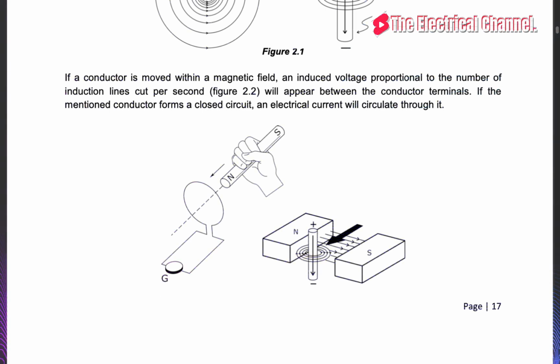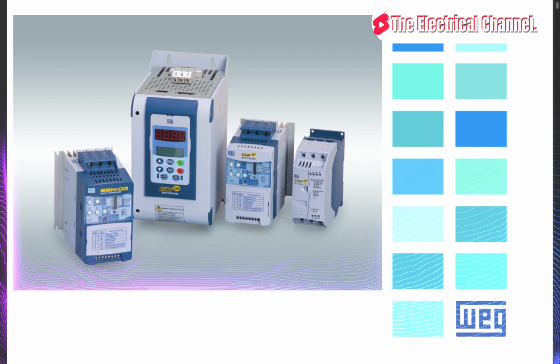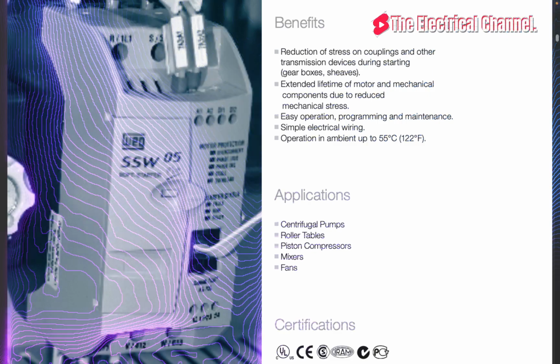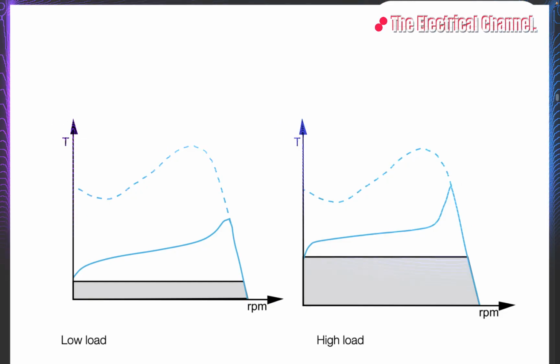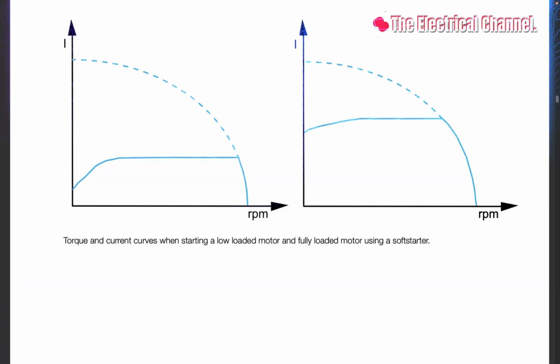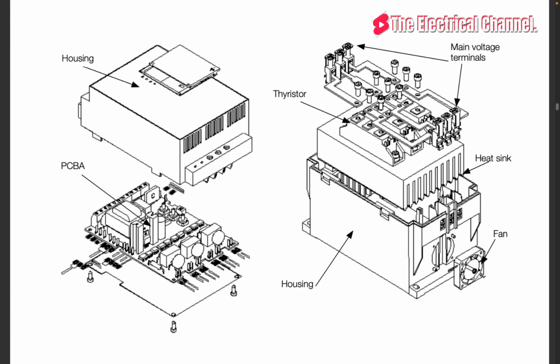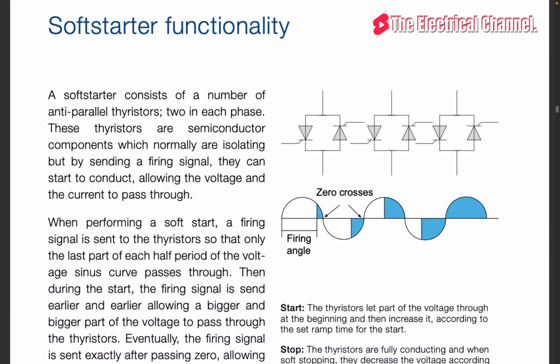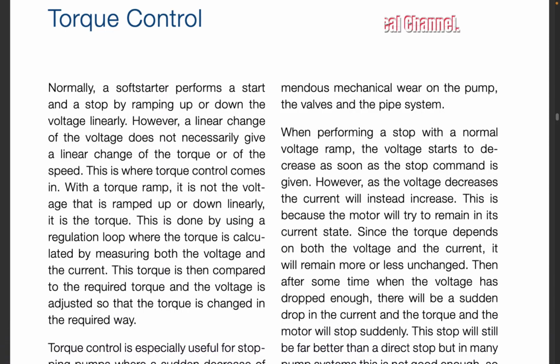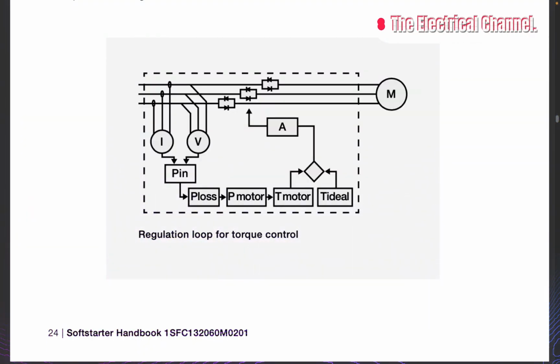A soft starter does not change the frequency or the speed like a drive. Instead, it ramps up the voltage applied to the motor from the initial voltage to the full voltage. Initially, the voltage to the motor is so low that it's only able to adjust the play between the gear wheels, or stretching driving belts. To avoid sudden jerks during the start, the voltage and torque gradually increase so that the machinery starts to accelerate.